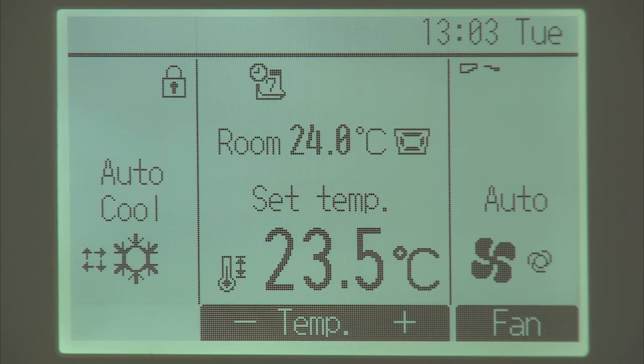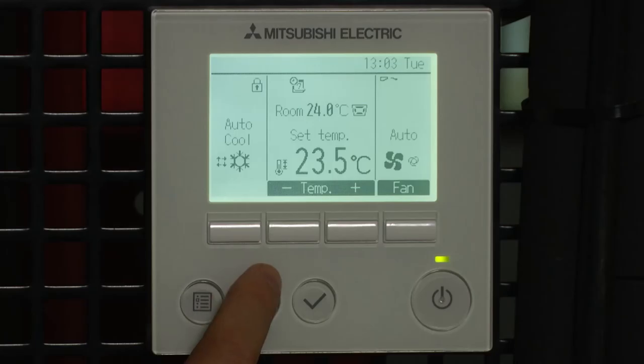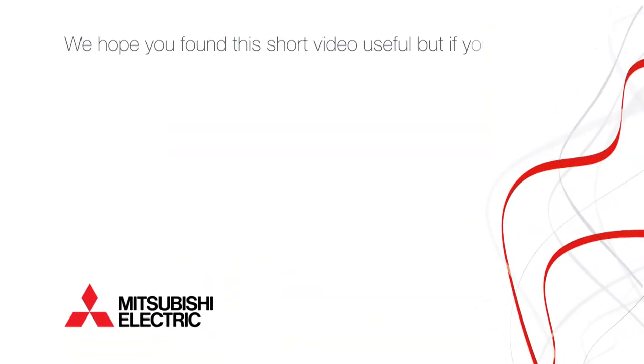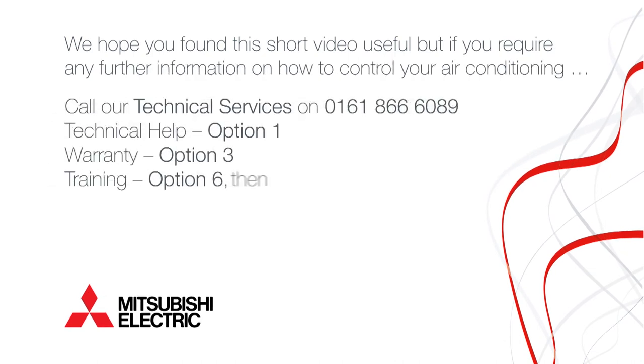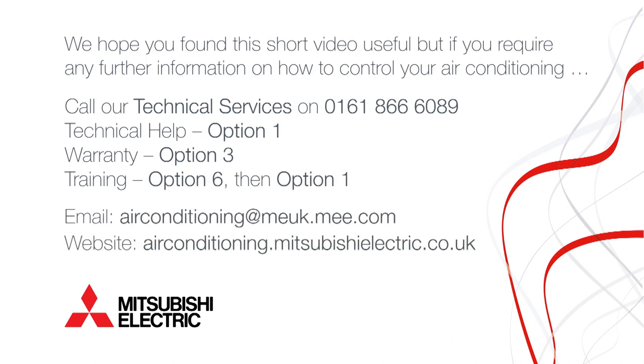Now it's obviously locked out the mode button. But by doing so there's no possibility of the system trying to start up in cooling mode with a room temperature of 22 degrees when you need heating in the room. You're always going to fix the settings.